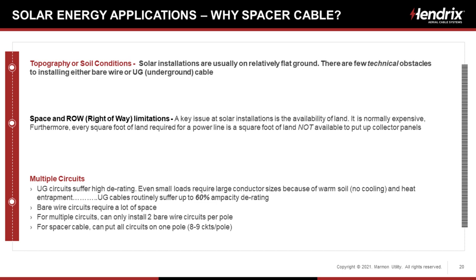And when we talk about multiple circuits, underground circuits suffer high derating. We'll talk about that in a little bit. But even small loads require massively large conductor sizes because of the warm soil, there's no cooling, and the heat entrapment. Underground cables at these solar facilities routinely suffer up to 60% ampacity derating. Well, we say we'll go to bare wire. We love bare wire, but that requires a lot of space because I can only get two circuits on a pole. Yeah, I maybe get three circuits on a pole, but nobody will work on it. And for spacer cable, we can put all of the circuits on a pole, whether that's 2, 3, 4, 10, 15, what have you. So there are no limitations in terms of spacer cable.